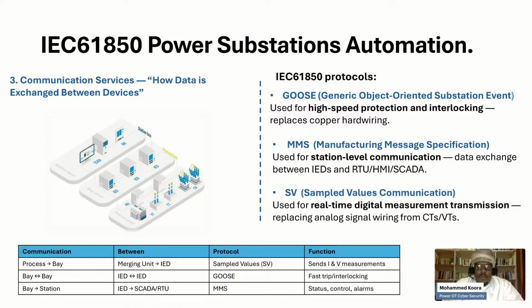That will help, because when we talk about GOOSE, imagine GOOSE, we are talking about 3 milliseconds traveling. So between the CT and the IEDs, we try to use the SV protocol, which is faster than that GOOSE protocol, in microseconds. So each different layer has different rules and different protocols to communicate.